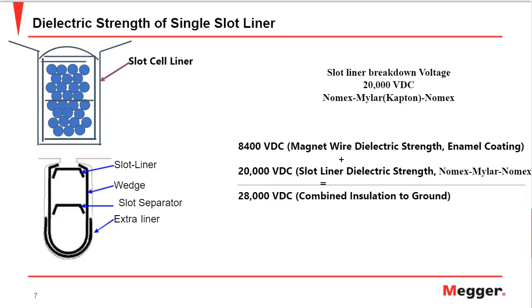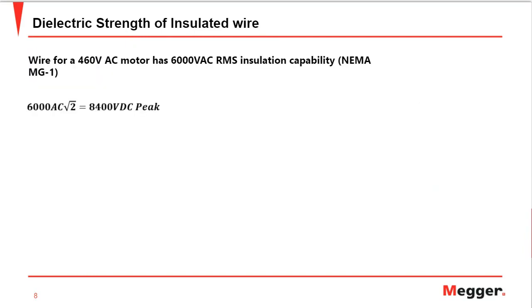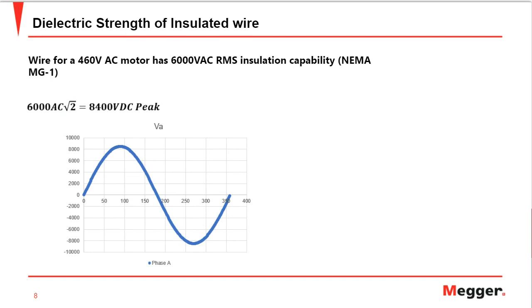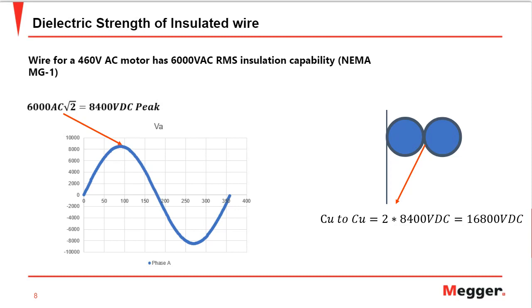Next we'll move to the dielectric strength of an insulated wire. As we've seen in the previous case, one conductor, which is enamel coated, has a dielectric strength of 8,400 volt DC peak, and 6,000 volt AC is the RMS insulation capability. So that's for one conductor. If two conductors are adjacent side to side within the same coil, it gives us a total insulation strength of 16,800 volt DC, which is pretty good.